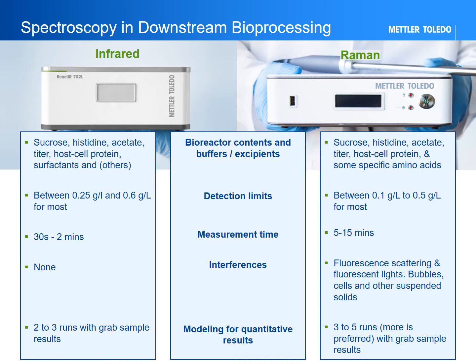So what is spectroscopy capable of? Looking at a side-by-side comparison of a mid-infrared FTIR system and a comparable Raman system, we can see quite a lot of similarities. In most cases, molecules which are strong for Raman do not have a similarly strong absorbance for mid-infrared FTIR — but the reverse also generally holds true. The two technologies therefore provide complementary information, and sometimes one method is genuinely a better fit than another.